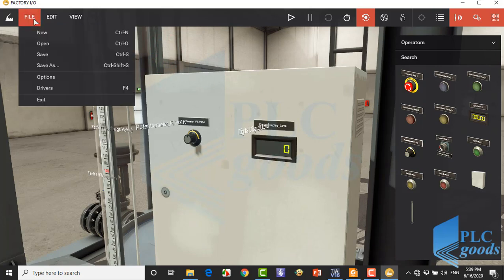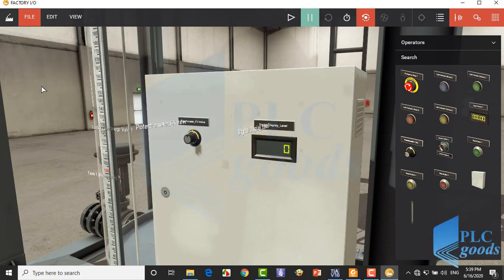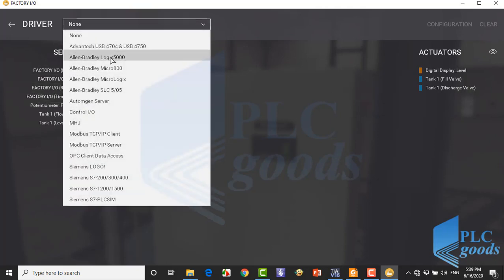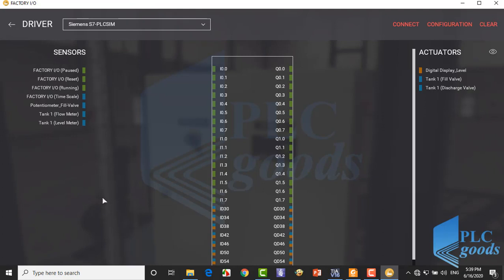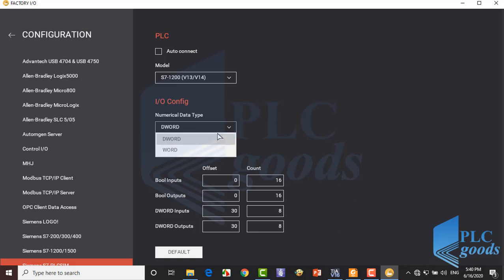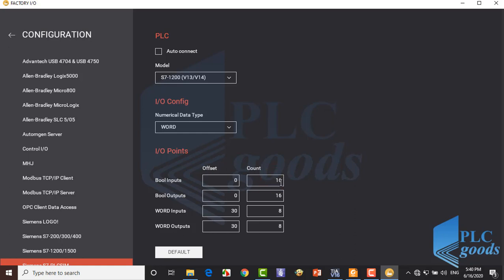Now let's click on file menu and select drivers to set PLC connection. We're going to use Siemens S7 PLC SIM. Naturally we don't need these digital input output. Click here to configure PLC. Let's select word type for PLC analog input output. Here at the first column we determine start addresses and at the second column we select how many input or output we need. Let's write 0 here because we don't need any digital input output. Finally we need two analog inputs and two analog outputs and define number 30 for their start addresses.